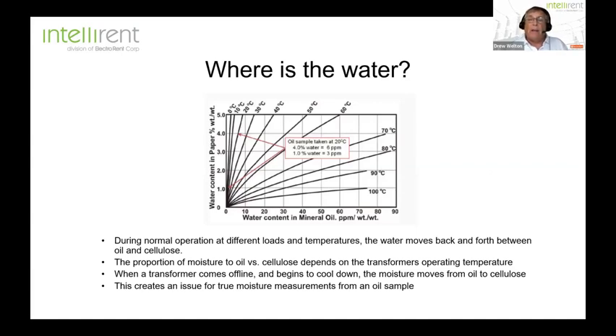Okay, now what is the problem with getting an actual or good measurement of the moisture content in the insulation? Well, what we know is that when you take a transformer offline and it starts to cool down, the water moves from the oil back into the insulation and it hides in little areas, little pockets in the solid insulation, spacers and barriers. And what happens is that creates inaccuracies in terms of what we measure in our ppm. So this is why we apply typically for many, many years what we call equilibrium curves. And that means that we take the oil temperature when we take the sample and we record that and supply that with our DGA analysis. And then the lab will try and estimate what the actual moisture content is with that temperature correction. But there's a lot of problems associated with that. The problems associated with the fact that you could have a bad sample.